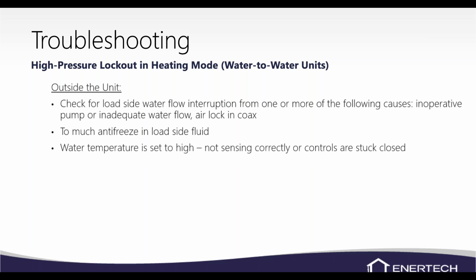Water temperature set too high. Normally we don't want the water leaving that unit, I would say anything more than about 120 degrees. If we start getting into the WT unit and we're running about 130 coming into the unit, we're going to cause the water leaving the unit to be somewhere around 140 degrees. So we could definitely run into some problems with high discharge pressure when we get that high temperature. Lower water temperatures are better. Obviously, the unit's going to run more efficient and it'll last longer.